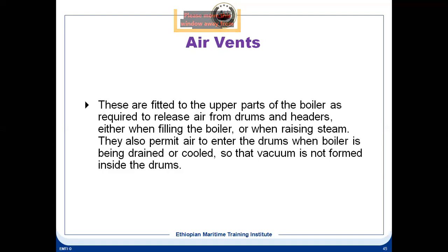So for that, when you are firing up the boiler, the air vent has to be kept open so that all the air from the boiler is completely vented out. Again, when you are cooling down a boiler, the boiler should not be allowed to go into vacuum. A boiler can take a certain amount of pressure, but normally it cannot take too much vacuum. So you should allow the air to enter when the boiler is being allowed to cool down. For that, you need the air vent.